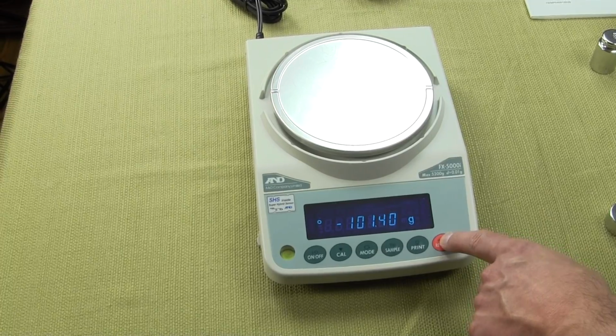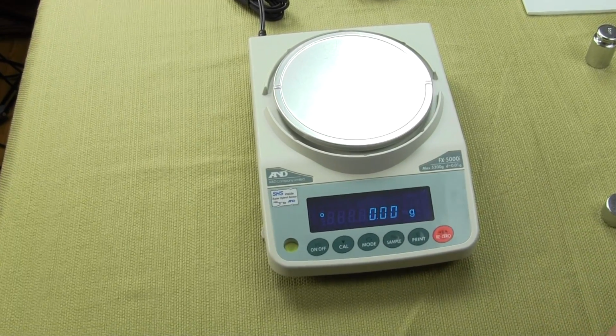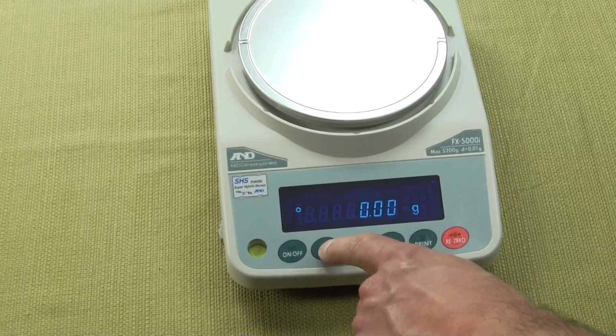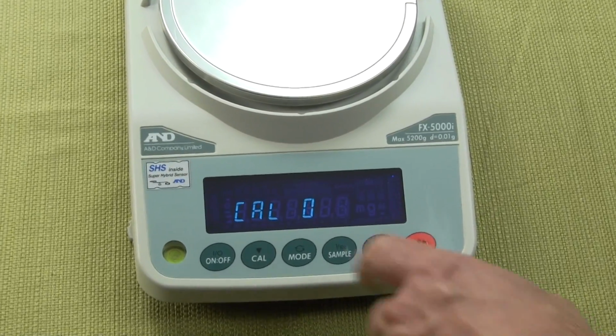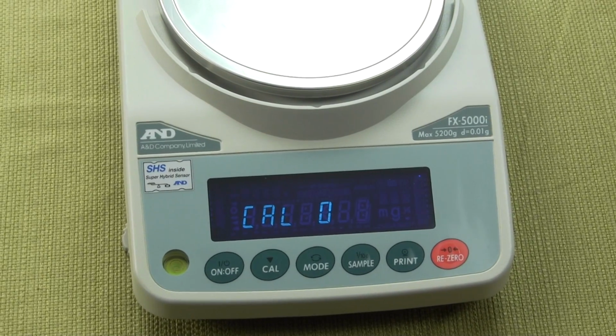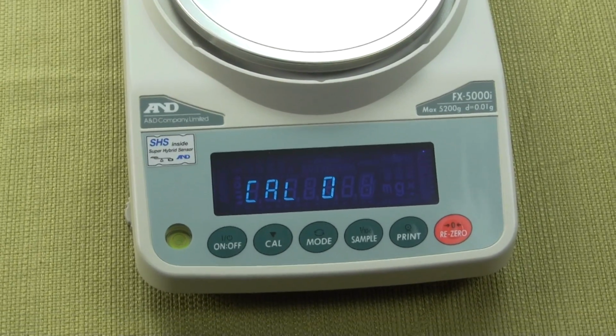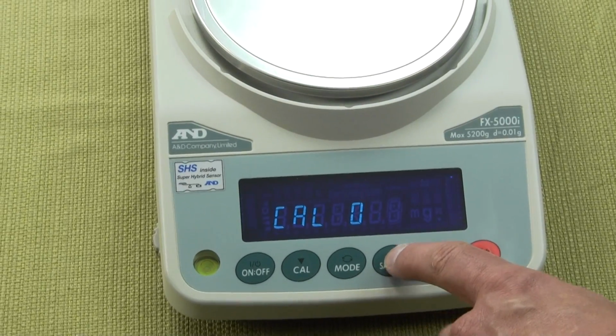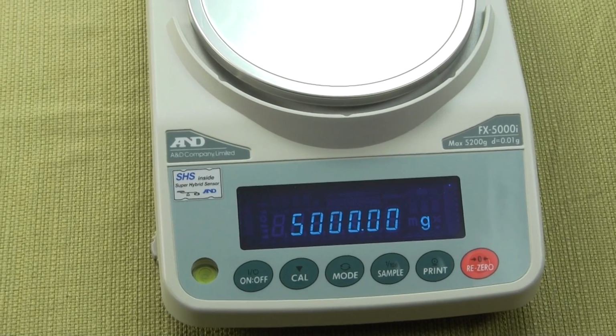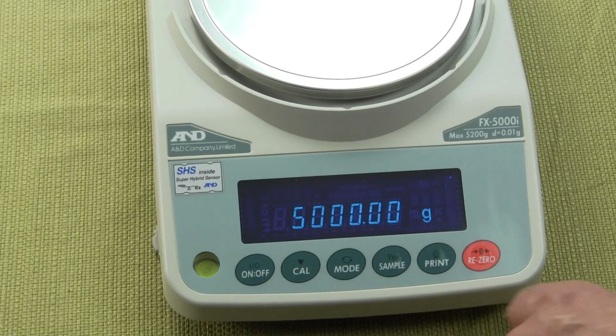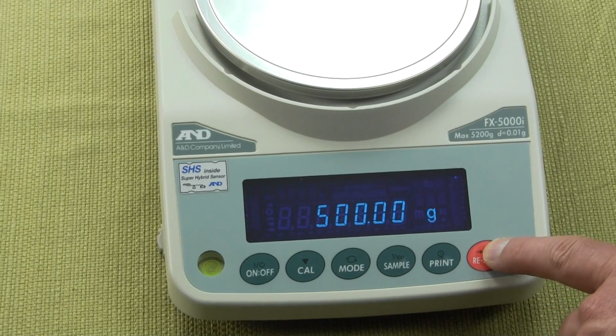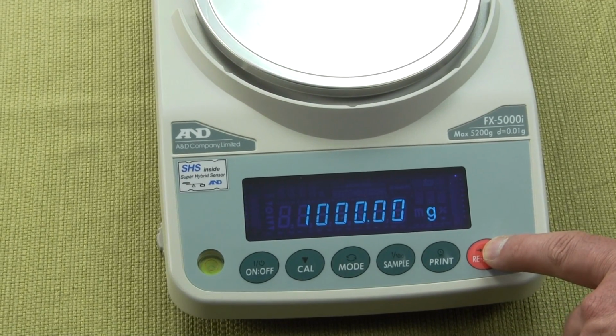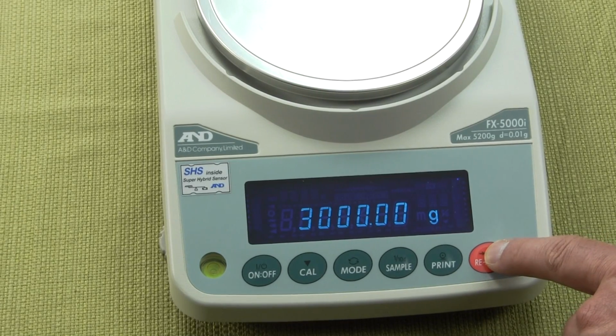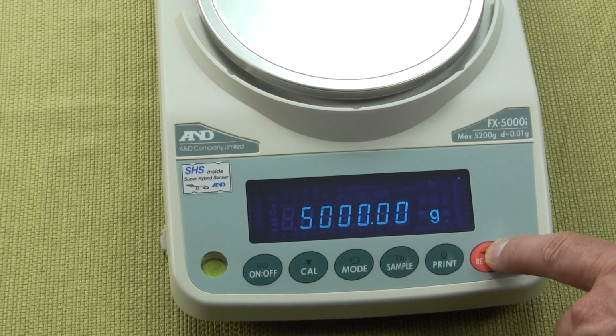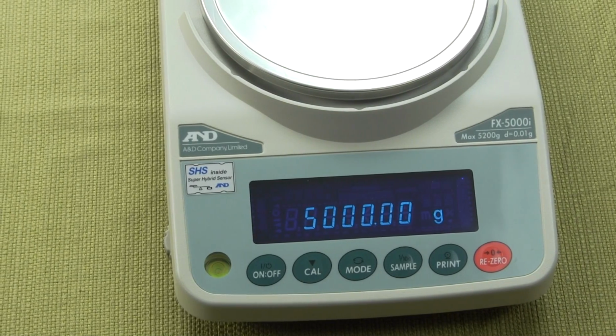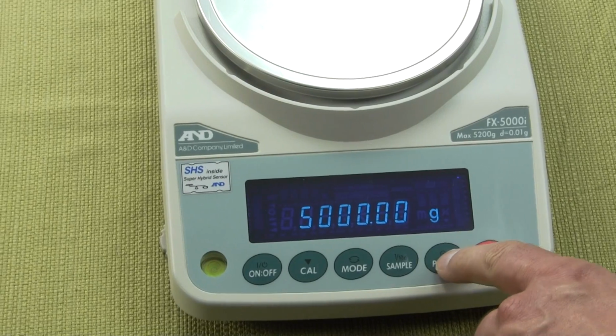So I want to go over calibration so we can calibrate this balance for you. So the first thing you want to do is zero the balance out. And to perform calibration, one simply presses the cal button. It says cal out and then it says cal 0. Now here, if you want to change the calibration weight, it's pretty simple. All you have to do is press the sample key and you'll see we're at 5,000 right now. We can change this by pressing the re-zero key, and you'll notice we can calibrate it with 500, 1,000, 2,000, 3,000, 4,000, and we're back to 5,000. So we'll leave it on at 5,000, and now we need to store it. To store it, you want to hit the print button.